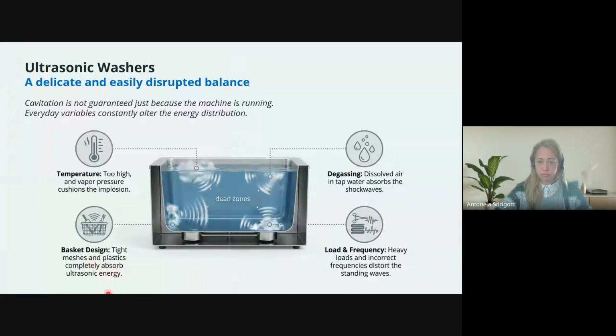Okay? Of course, what will affect the efficiency is the load and the frequency of the transducers, how the transducers are working. If I put heavy load or I put too much load inside, I will obviously be decreasing cavitation energy delivered to all the instruments. So overloading, of course, is a disadvantage.